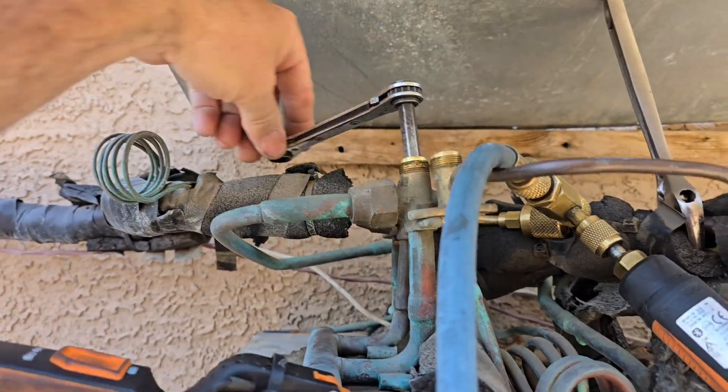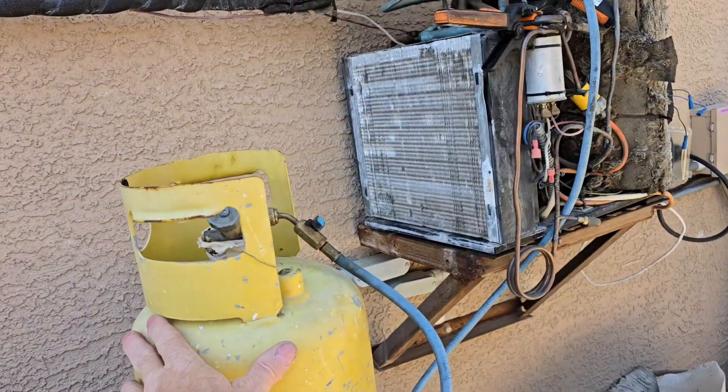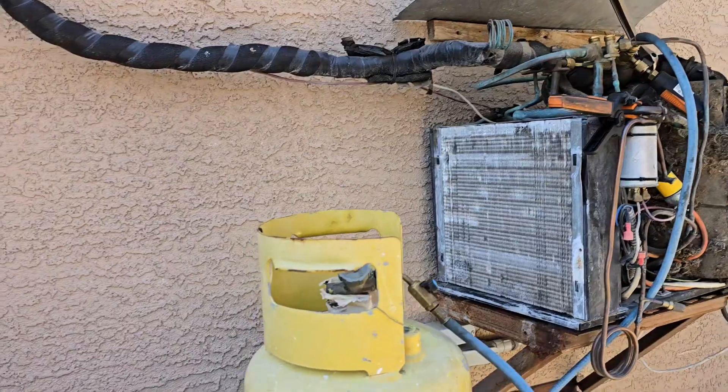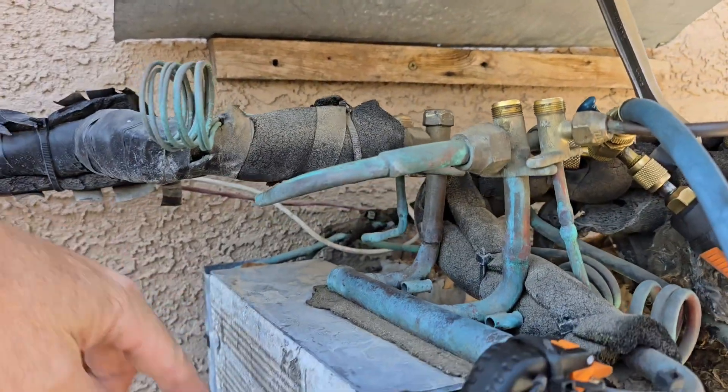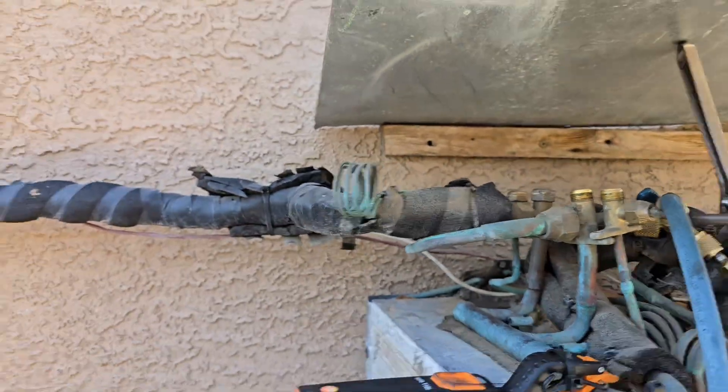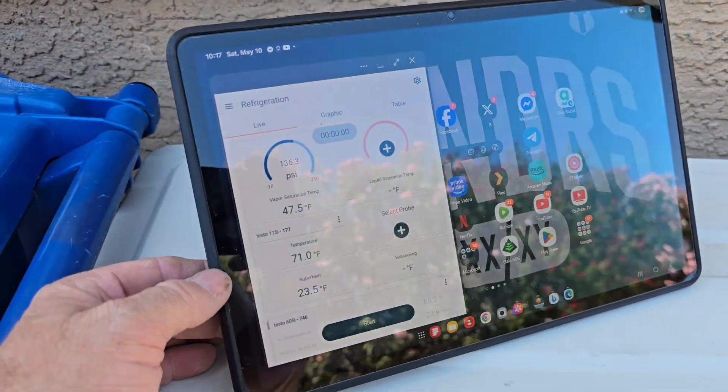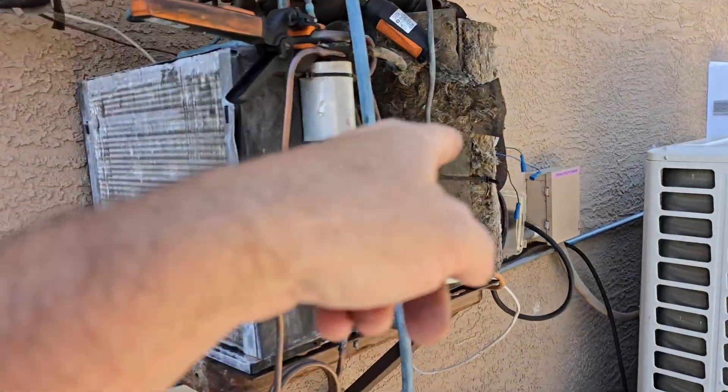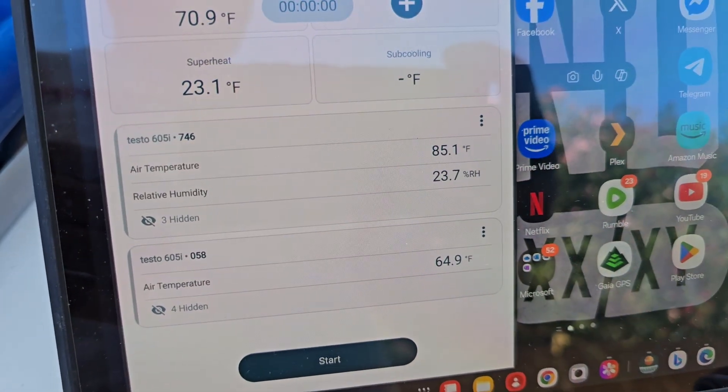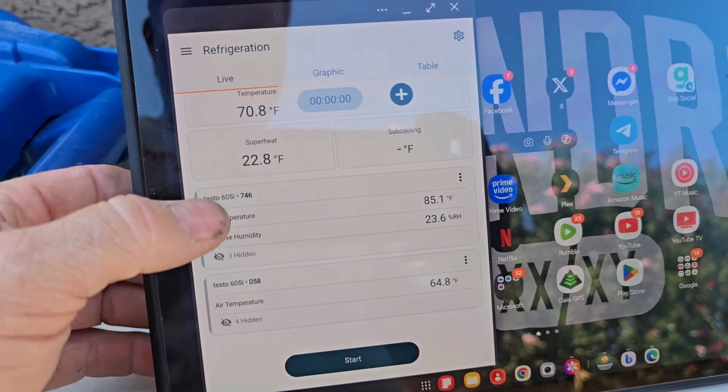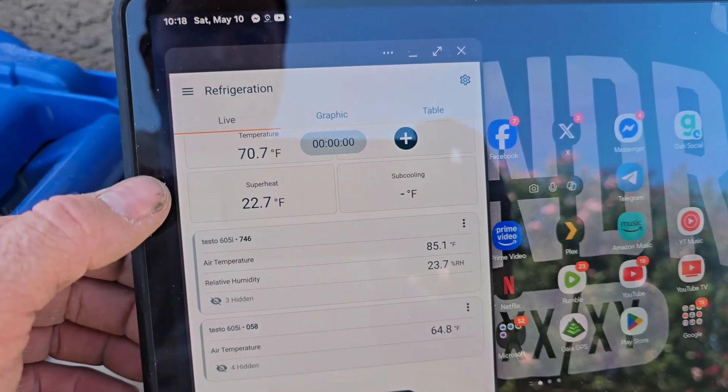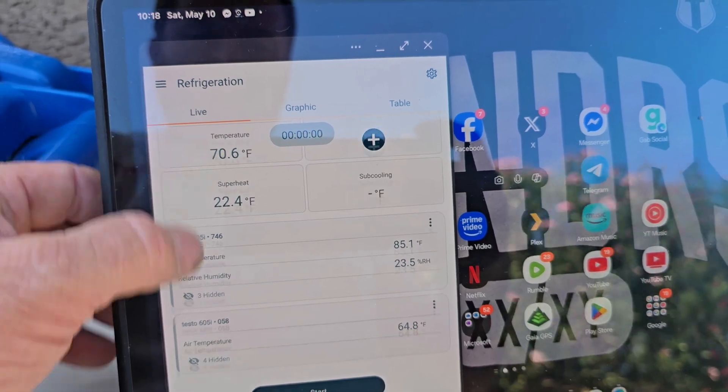Already got the liquid line closed. I'm just closing the suction line now. I'm going to let it run, just see if I have to put just a couple ounces back into it since I did pull out a little bit when I took that off. It's charged kind of how it sits here, so pretty critical charge probably. It's a capillary tube system. There's capillary tubes back there feeding this coil and then there's capillary tubes right here feeding the indoor high wall, which works great. The indoor unit running. I dropped the fan speed down to medium since that is a one ton. This is like a half ton compressor in here. I got about 136, 23 superheat. 85 in the room, it's actually dropping the temperature of the room. It was 90 and 65 degrees blowing out. It's like textbook 20 degrees split right there. That temperature is not critical. It's more this is more geared for heating water, but you know, kind of get this dialed in like that, so that's pretty good. I'm going to go ahead and pull my gauges and just let this unit run a few minutes and then it should be all set.